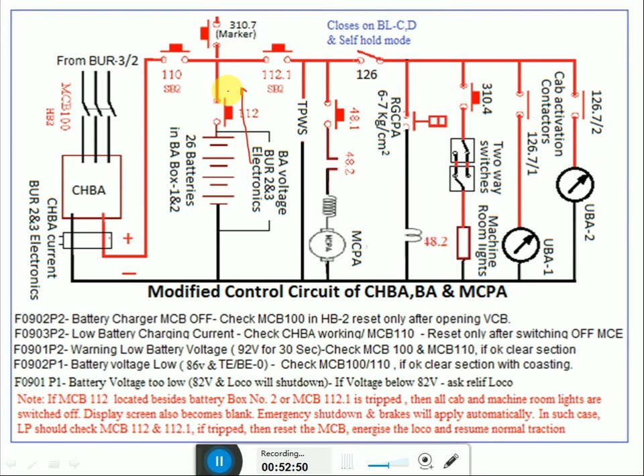If any MCB like 100 trips in HB2, we will get a message F0902P2: Battery charger MCB off. So open the VCB and reset the MCB. If the charger is not working or MCB 110 trips, we will get a message F0903P2: Low battery charging current. While working a train, we have to ensure MCB 100 and 110 are in good condition, not tripped, and 112.1 and 112 also.